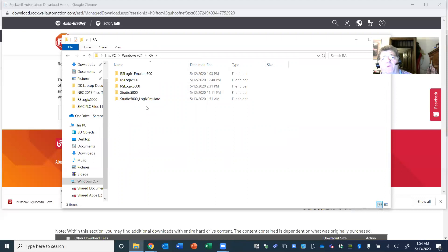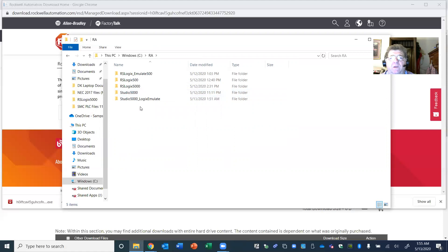Before I did this one, I had downloaded Studio 5000, which is the PLC logic program you use to create programs and download into a PLC. The emulator is going to take the place of a real PLC on your computer. Once you use Studio 5000 to create logic programs, you'll download them from Studio 5000 into the emulator, and the emulator will mimic a hardware PLC. Our next step is to go inside the Emulate folder and look for a setup file that will do an automatic setup — but you have to trigger it by hand.